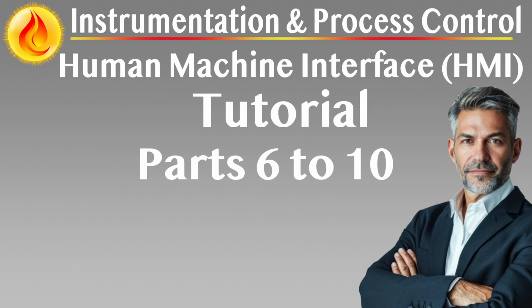Secondary console: 2 VDUs with 1 keyboard and pointer, used during plant startups, emergencies, or operational peaks. This may be shared between units. Supervisory console: a single VDU with keyboard and pointer, often located in an adjacent office, used by operations managers, engineers, or technologists for read-only monitoring. With authorization, this can be temporarily switched to read-write for tuning or system maintenance. Additional consoles may be placed remotely for simple or standalone units such as water treatment systems or product blending facilities.